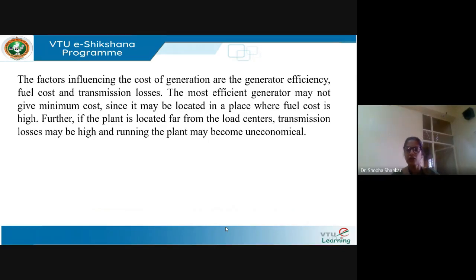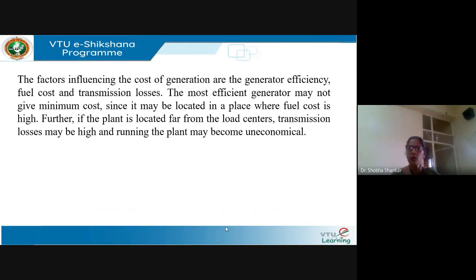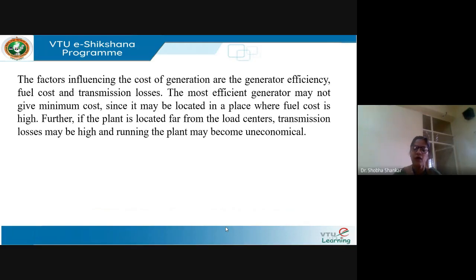The factors which influence the cost of generation are: generator efficiency, fuel cost, and transmission losses. Even if a generator has very high efficiency, that alone does not ensure that the cost of generating power using that generator is minimum. This is because the generator may be located in a place where fuel cost is very high, and load centers are located far from the generator points, so transmission losses would also be high, making running the plant uneconomical.